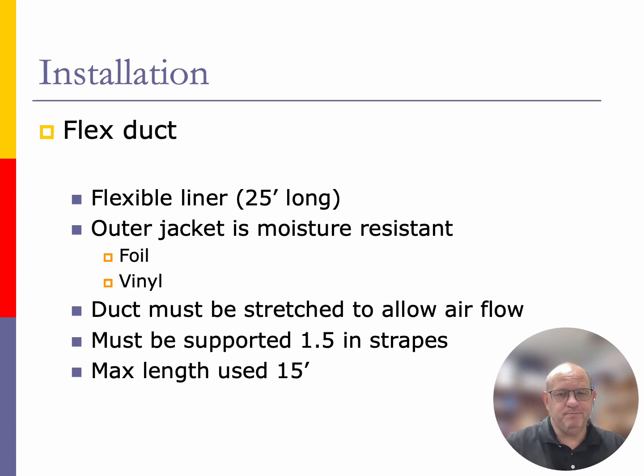When you look at flex duct installation, the boxes are going to come in 25-foot lengths. Okay, but that does not mean that you can run these boxes 25 feet. I've seen a lot of bad installers, and they'll run 75 feet of flexible duct. That's not a good idea. There's a lot of air restriction when it comes to these flexible pipes because of the rigid wire that they have run through that particular pipe.